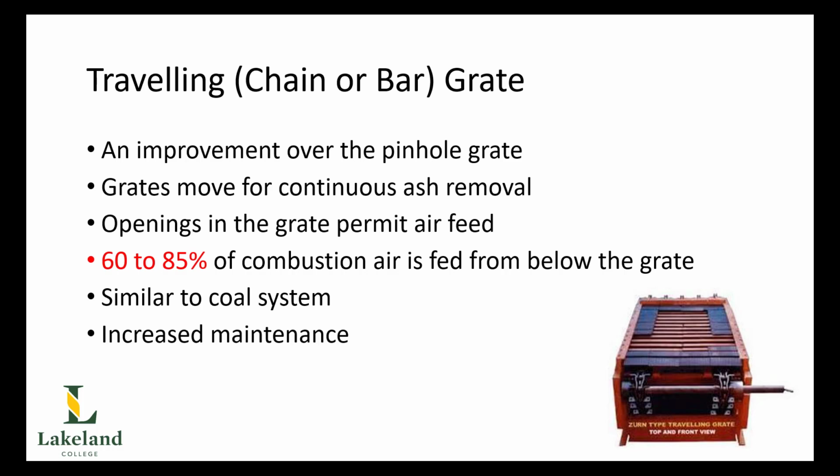And it's only going to move at very slow speeds, typically about 5 millimeters per second, but of course that's going to depend upon the combustion time required to completely combust the fuel. Either way, by the time the fuel reaches the end of our chain grate stoker, it's then going to drop off into the ash system and it will then be simply removed.